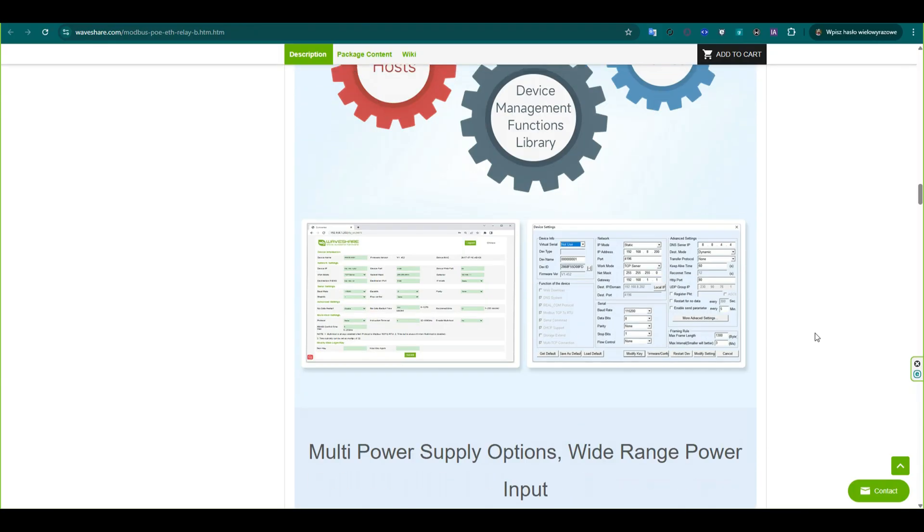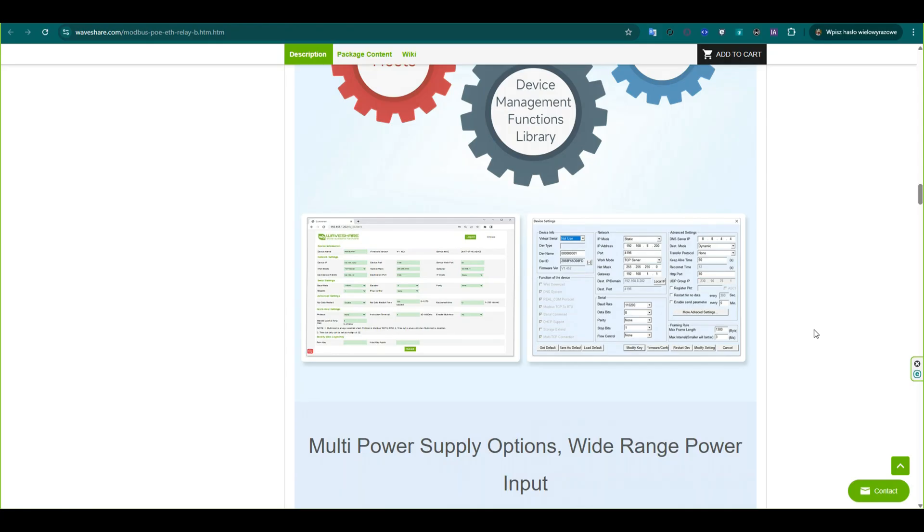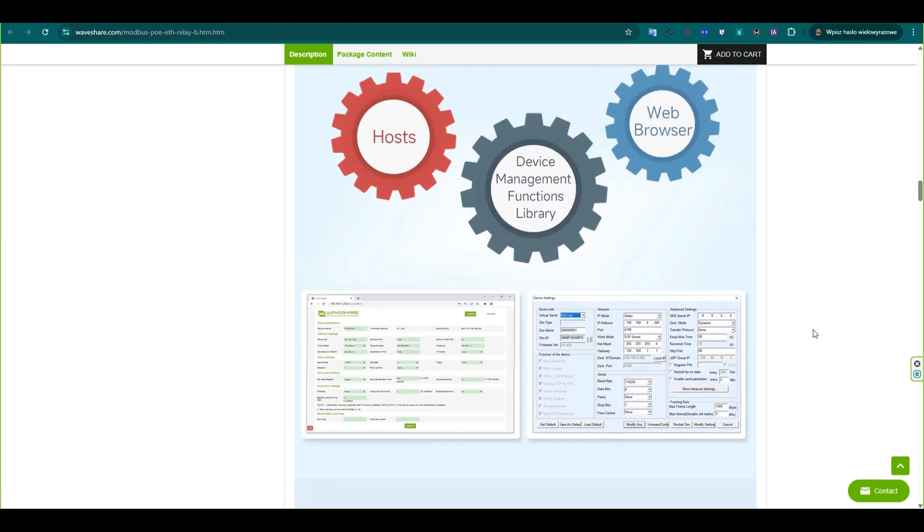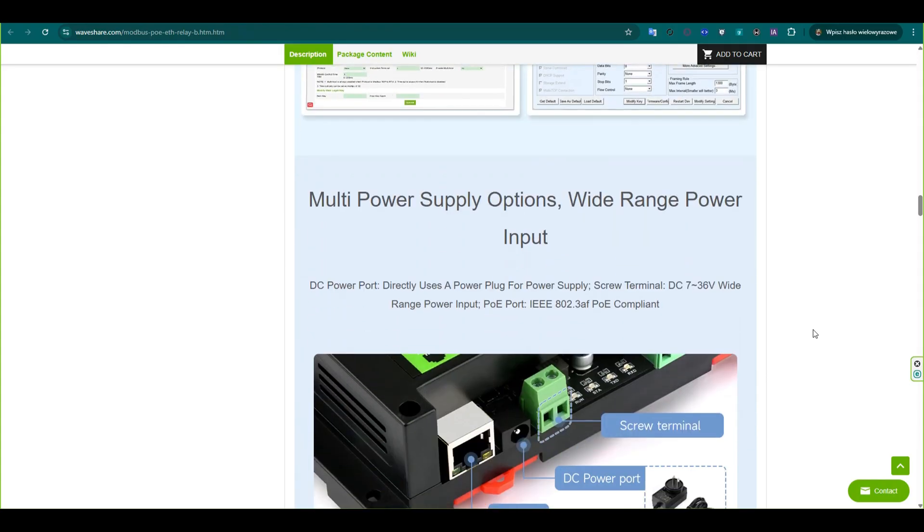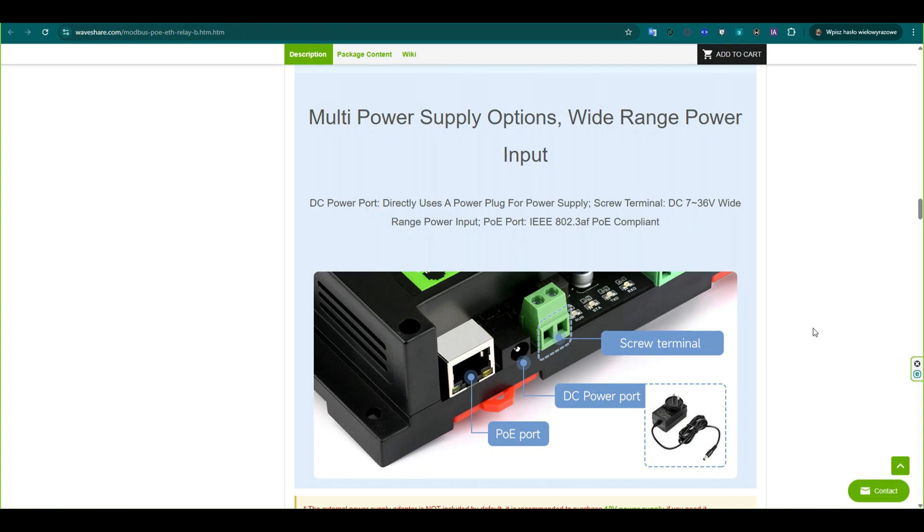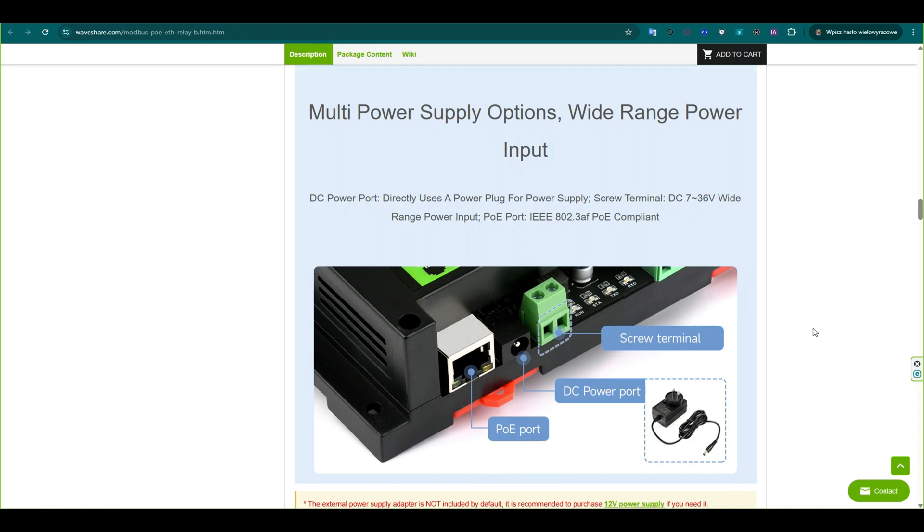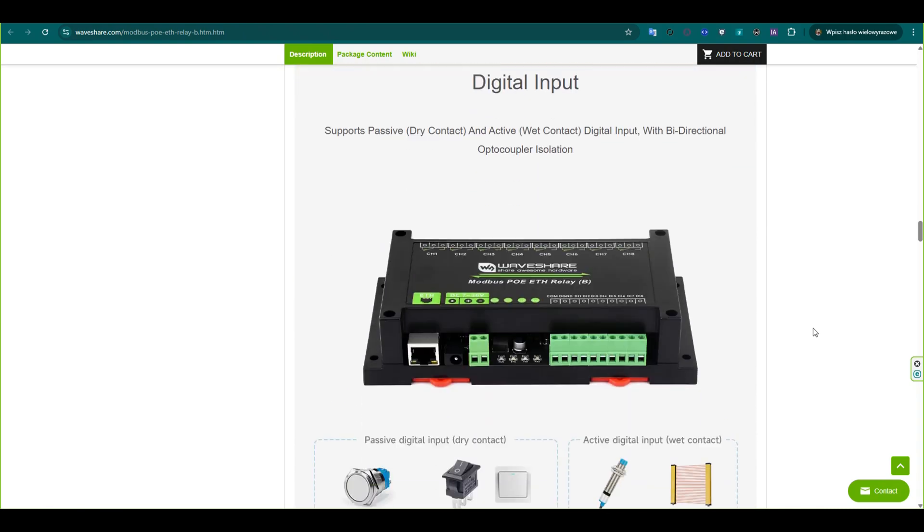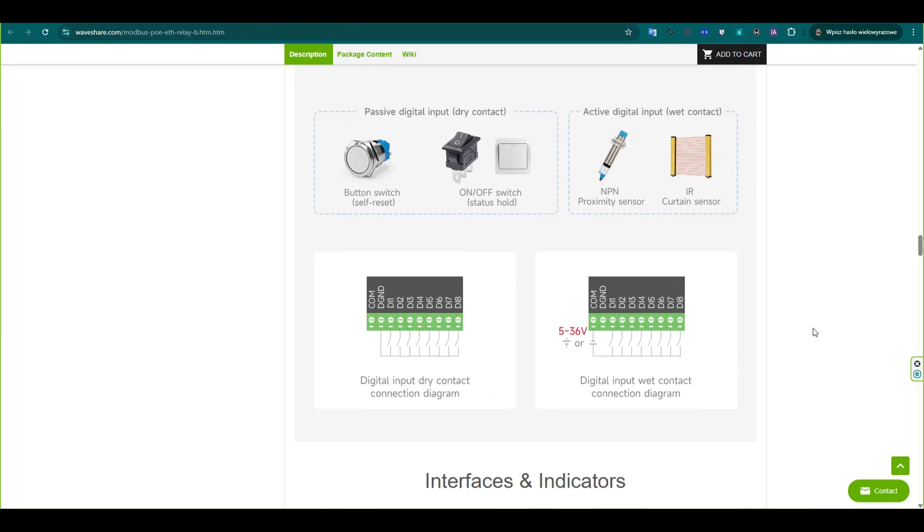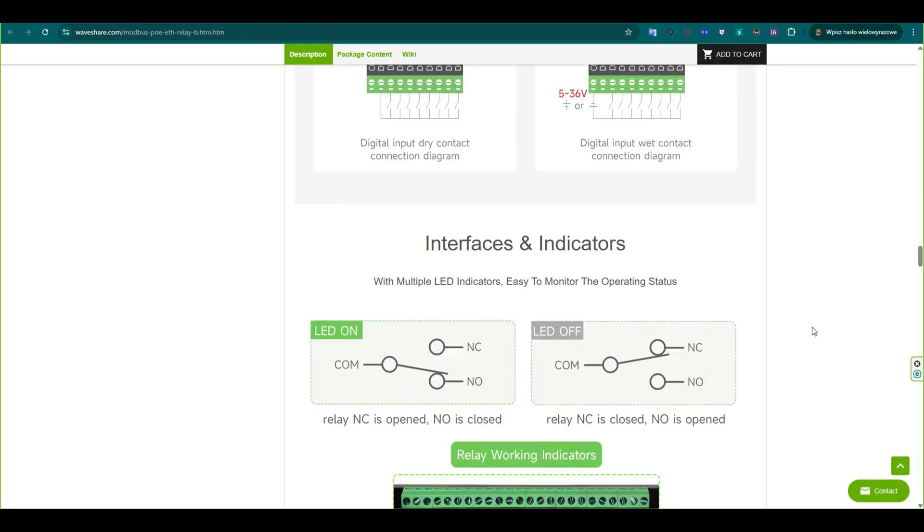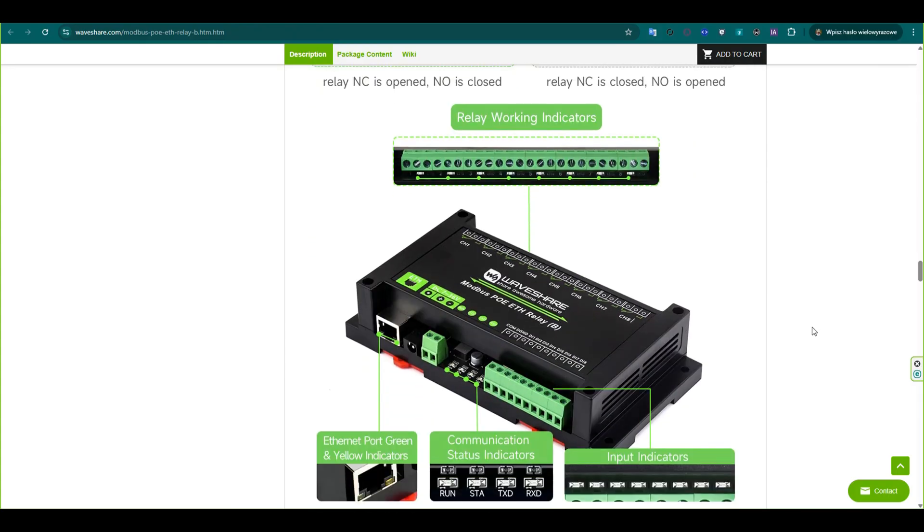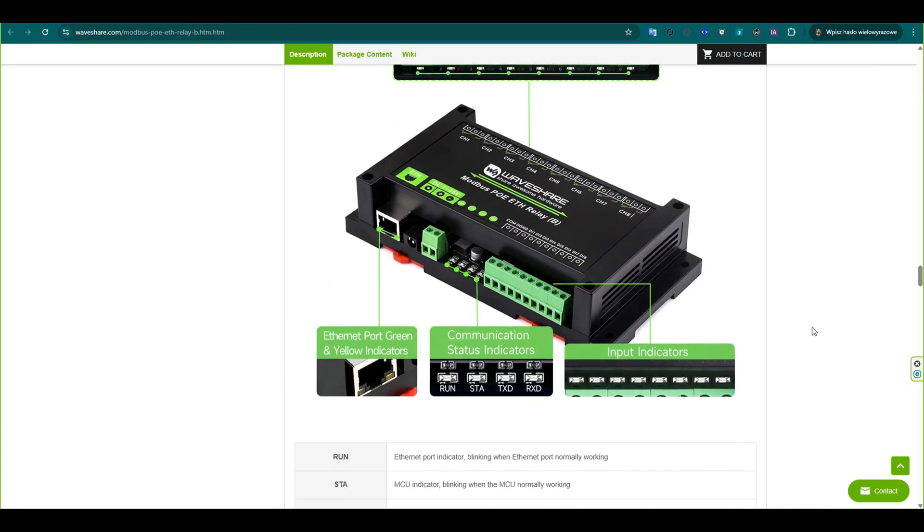The module supports configuration through both software and a web browser. It can obtain a dynamic IP via DHCP and connect to a domain name server using the DNS protocol, making network setup flexible and straightforward. It can be powered in three ways: via a DC power plug, a screw terminal supporting 7 to 36 volts DC or through a PoE port. The module supports both passive dry and active wet digital inputs with bi-directional optocoupler isolation for safety. It has multiple LED indicators, making it easy to monitor the operating status.